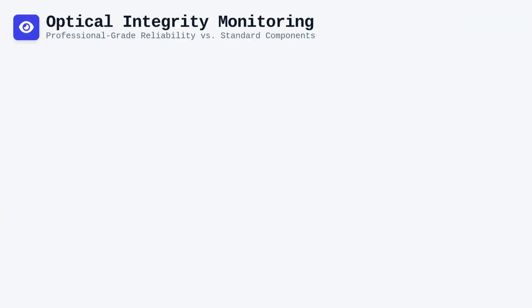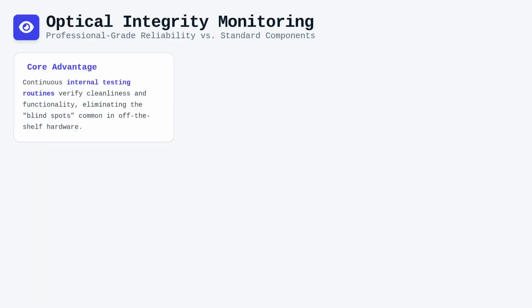Optical integrity monitoring is another critical aspect that separates professional-grade systems from simple, off-the-shelf components. Many modern detectors include internal testing routines that periodically verify the cleanliness and functionality of the optical window. If dust, oil, or chemical spray accumulates on the lens, the system reports a fault, ensuring that the sensor does not lose its ability to see the hazard. This is particularly vital in munitions storage or aircraft maintenance where the environmental conditions can change rapidly.